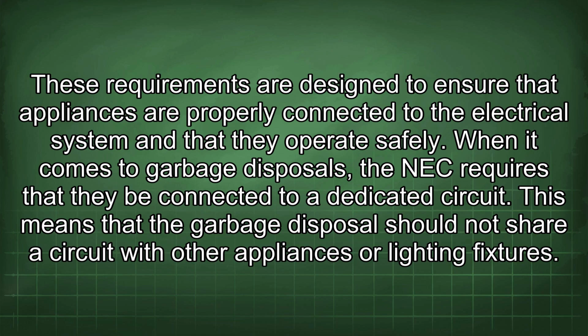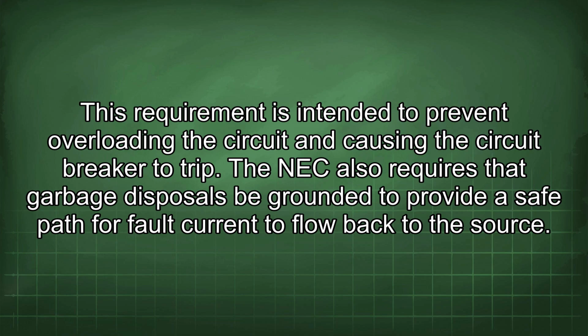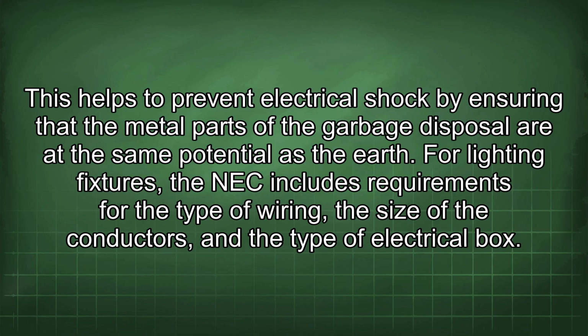When it comes to garbage disposals, the NEC requires that they be connected to a dedicated circuit. This means that the garbage disposal should not share a circuit with other appliances or lighting fixtures. This requirement is intended to prevent overloading the circuit and causing the circuit breaker to trip. The NEC also requires that garbage disposals be grounded to provide a safe path for fault current to flow back to the source. This helps to prevent electrical shock by ensuring that the metal parts of the garbage disposal are at the same potential as the earth.